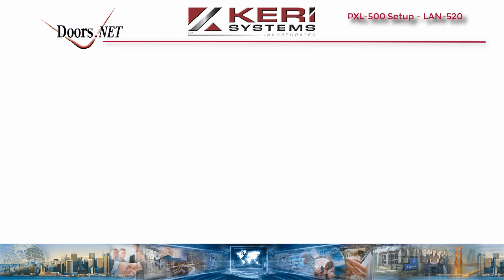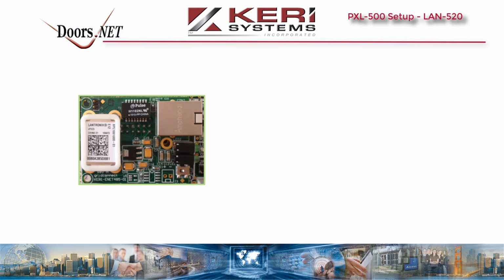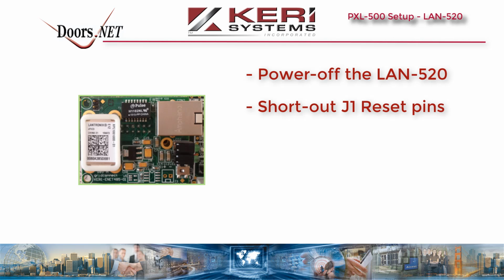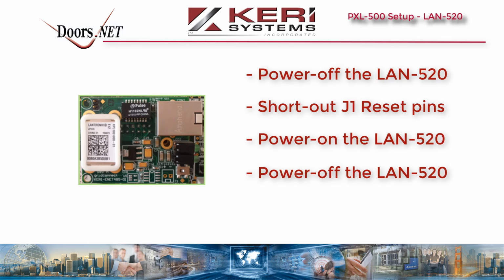Before setup, the LAN 520 must be factory reset. The factory reset procedure is as follows. Power the unit off. Place a jumper across both of the factory reset pins. Power the unit on. Power the unit off again. And then remove the jumper from the factory reset pins.